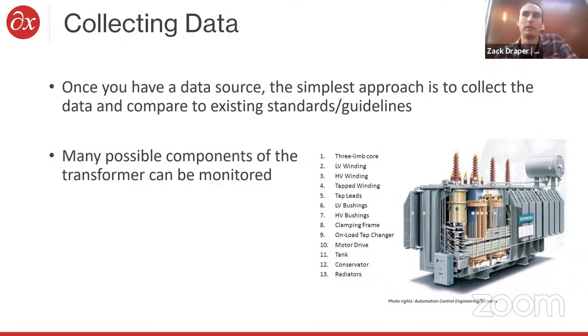There's many possible components to monitor. The three main ones in a transformer are the windings, LTC, and the bushings, all of which can be assessed with DGA to varying degrees, depending on the type of bushing or the type of LTC. But being able to tackle those three main failure modes is important in order to increase the reliability of operating a transformer.